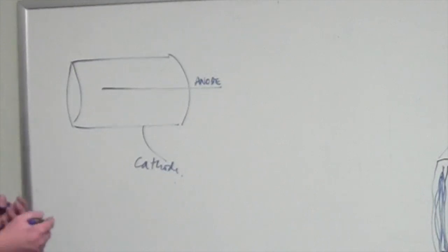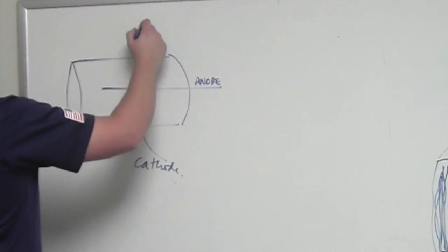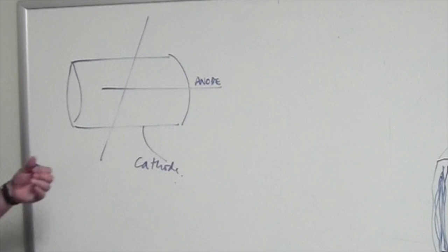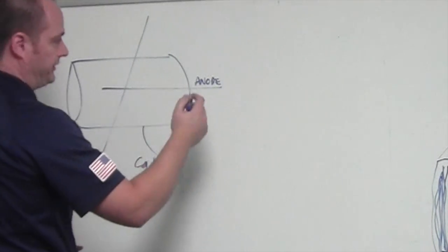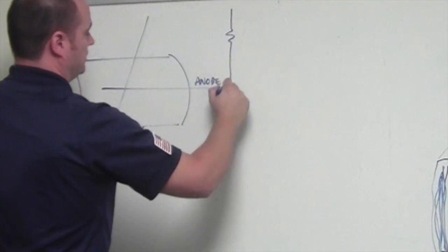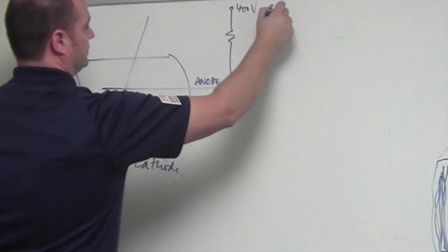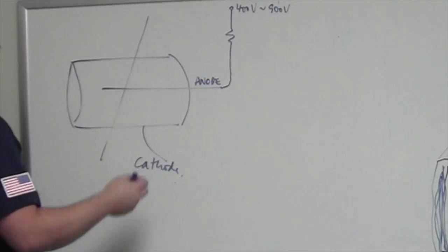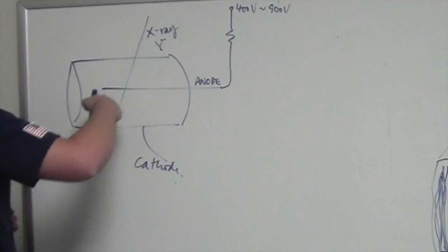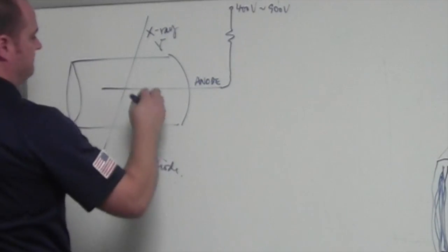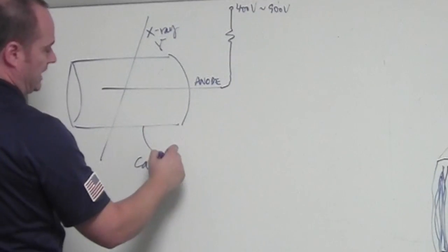The whole process of detecting radiation happens when an ionizing radiation particle, an x-ray or a gamma-ray, crosses the volume of this cylinder. The cylinder has gas inside and it is polarized with a high voltage, right? So you have, I can have here, four hundred volts to nine hundred volts depending on the GM tube that you're using. And so when this x-ray or gamma-ray hits this detector, an avalanche of ions is created, which then creates a signal out of the cathode.